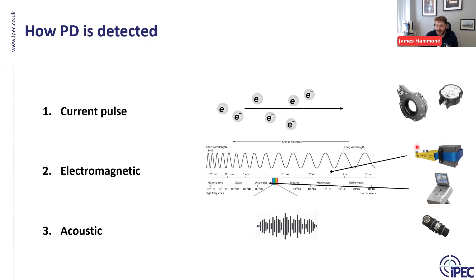However, if you've been into a substation, been under a power line, of course, you do hear that buzz, which is very recognizable and is an example of partial discharge occurring. So bringing it back to actual reality, something like a TEV sensor, a transient earth voltage sensor. This is detecting this movement of electrons, that current pulse. Say you have this partial discharge occurring here, it emits the energy and these electrons get pushed, or basically move around the metal surface, on the skin of the metal-clad surface, and then induce a voltage onto our TEV sensor.